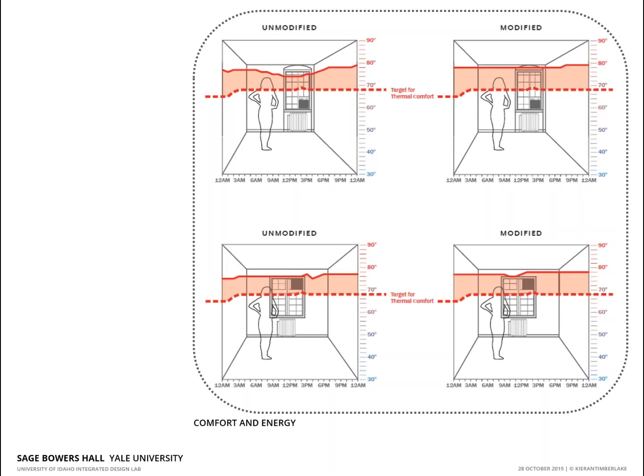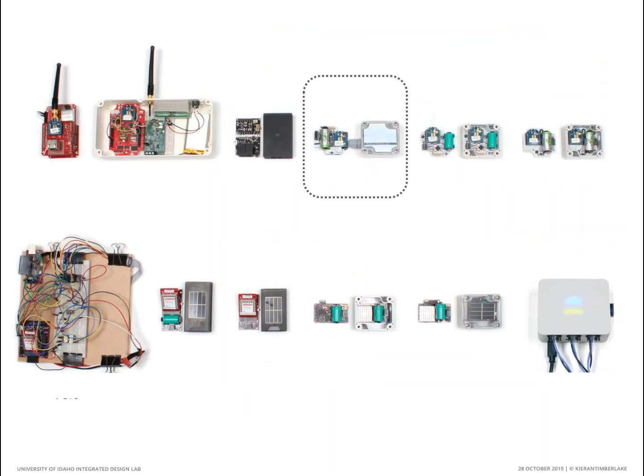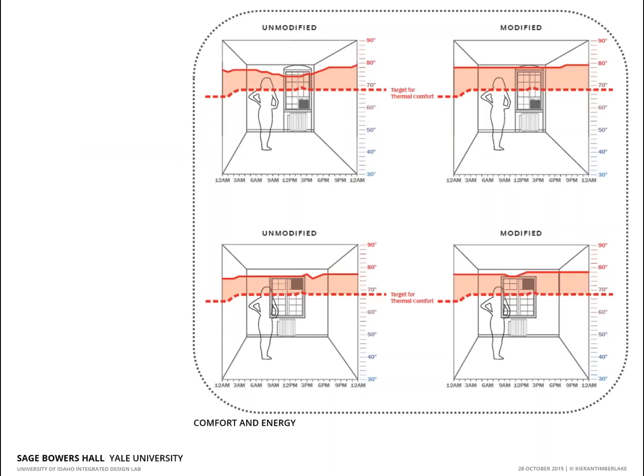The other thing that we noticed with this is that there was a location of a steam pipe within the building below a lot of the rooms we had modified. And we were seeing excessively high temperatures within this space. So as a result of that, with our modifications, because none of the other basic mechanical and infrastructural issues had been addressed, we're seeing excessively high temperatures within that space, ones that really made it incredibly uncomfortable. So through the monitoring, we're able to find out that basically, yes, you can do this. B, you incorporate some risk of increased weathering. And lastly, you have to worry about the overall infrastructure. You just can't throw up insulation and call it done. You actually have to start thinking about things like steam pipe location that might be actually right underneath your building that will be running all year, not only just in the wintertime.